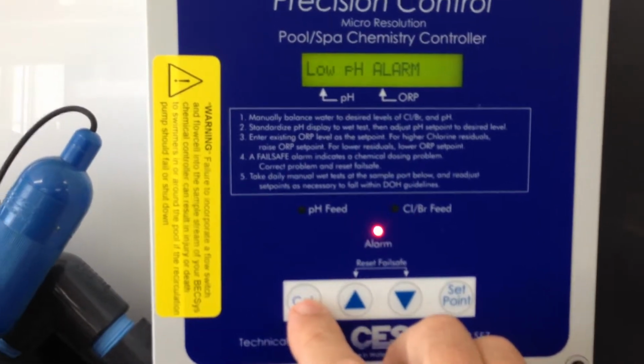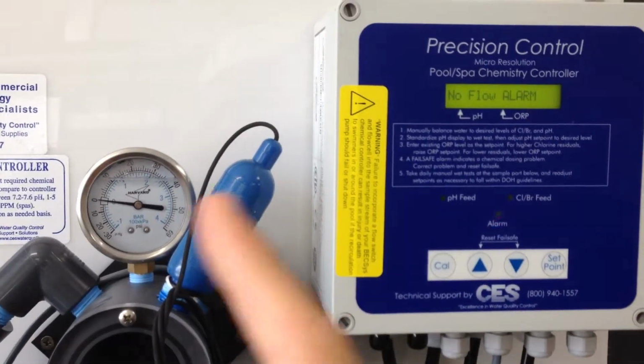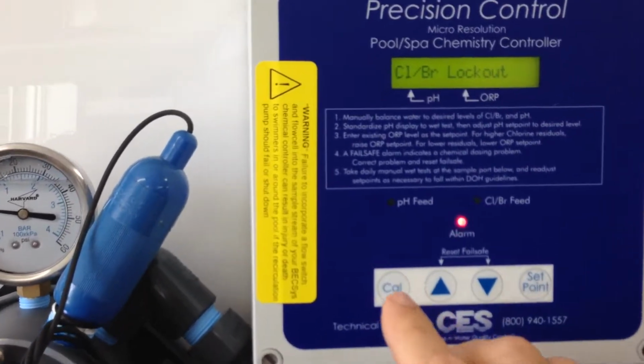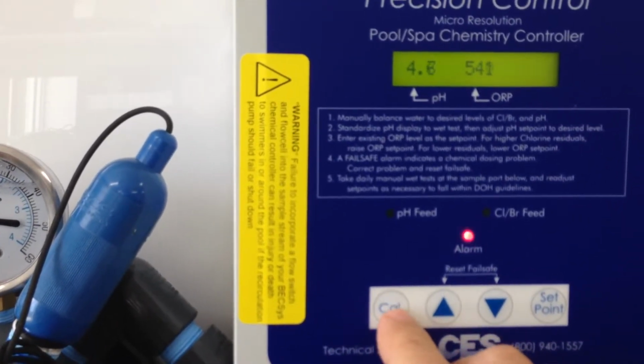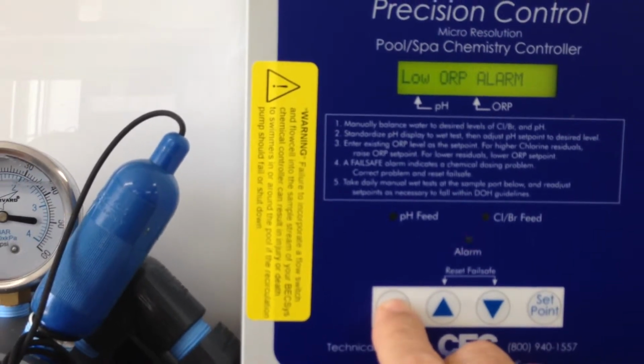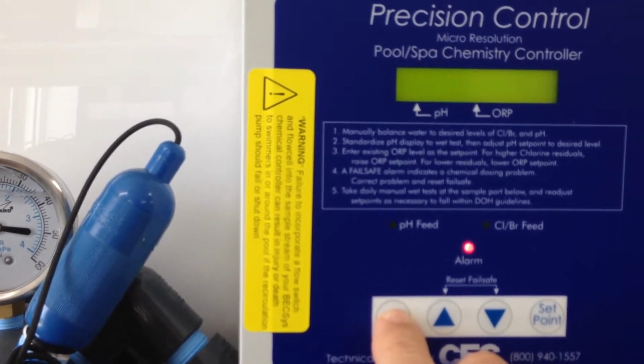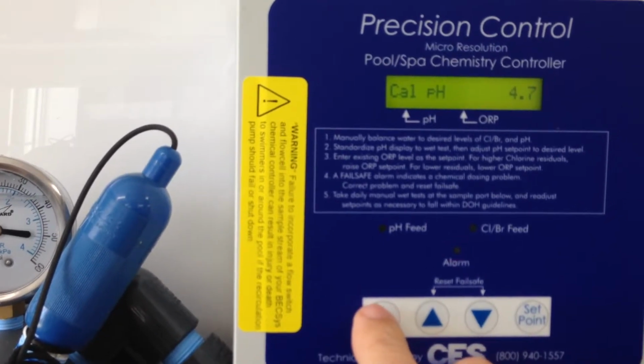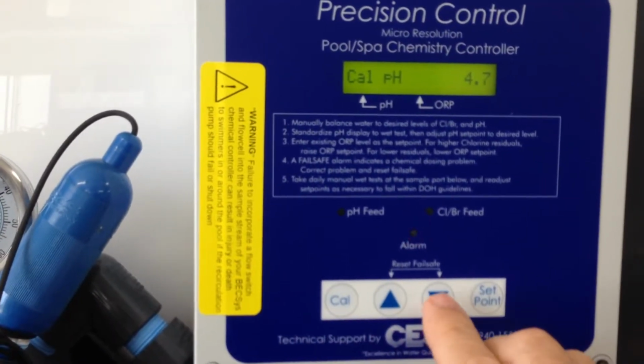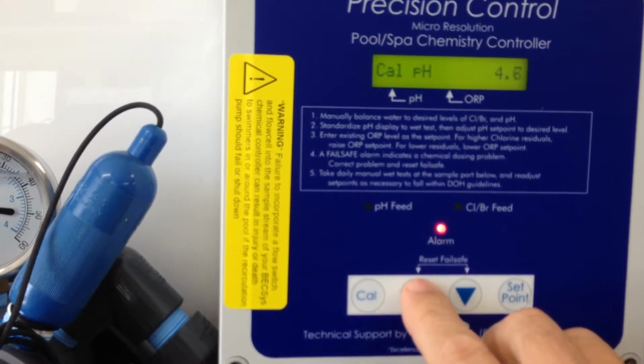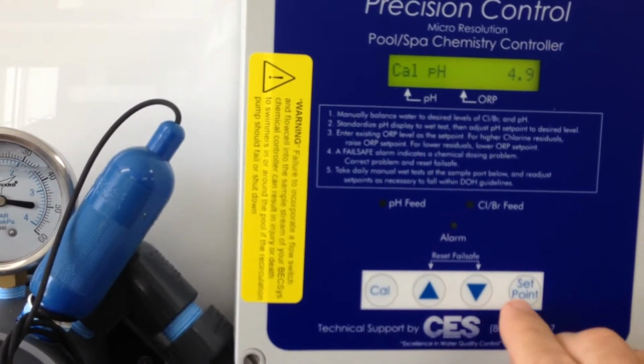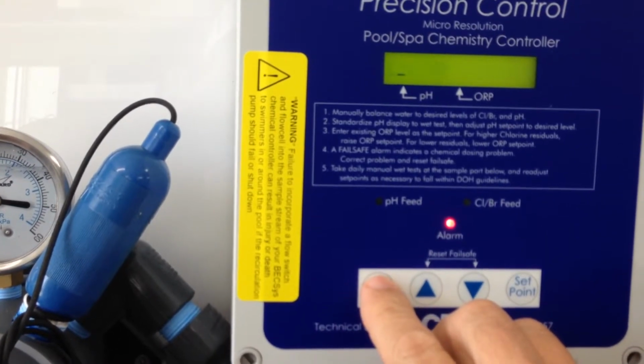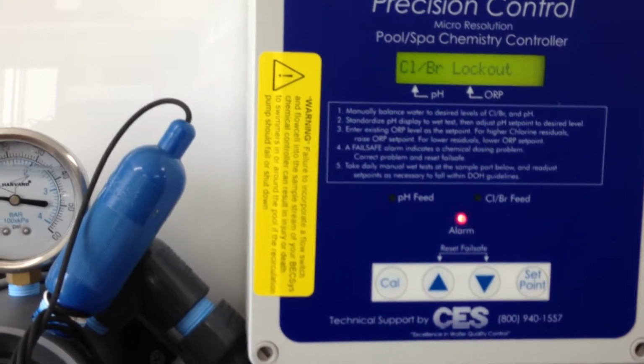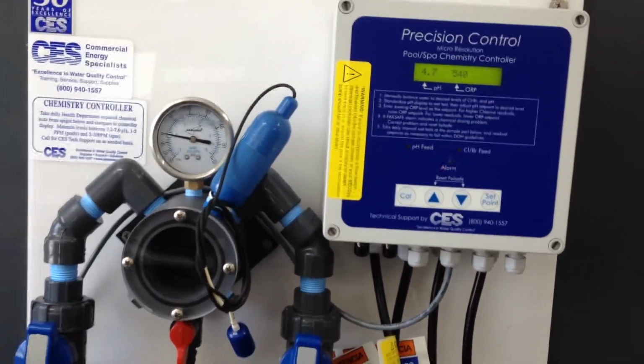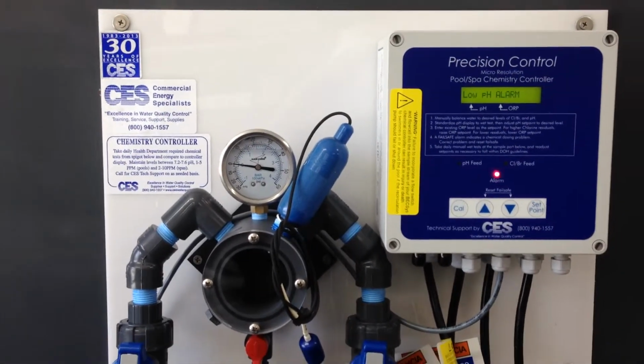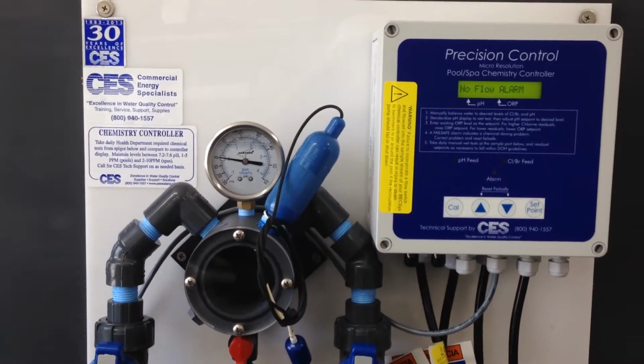The first thing you're going to do is let the probes wet in for a couple of hours, and then you're going to come in here, take a pH test with your test kit, press the calibrate button once and hold it, and then it's going to tell you calibrate pH, and you use the up and the down arrow so it matches your test kit. As soon as it matches the test kit, you press the calibrate button again, and that's it. There's no such thing as calibrating ORP, because it's like saying it's too hot outside, just go adjust the relative humidity of the temperature. It is what it is.